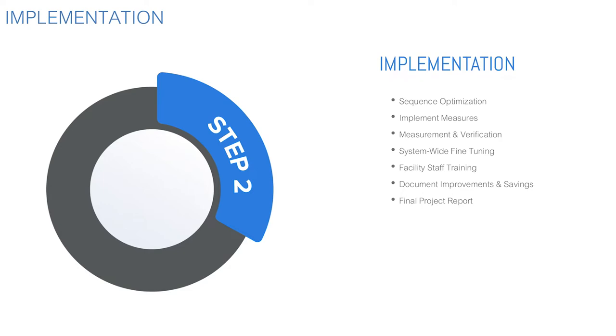Keep in mind, it is all about the sequence of operation. This is not one and done. We're in the facility for a full year, folks, working side by side with facility staff, training them. This is not just giving them a cookbook and handing it to the control vendor to program, then waiting to be told when it's done. This is working back to back with them. When it's done, we optimize the system and fine-tune it so we can get the best result for the client as weather changes, as load changes, as things change in the hospital or facility we're working on.